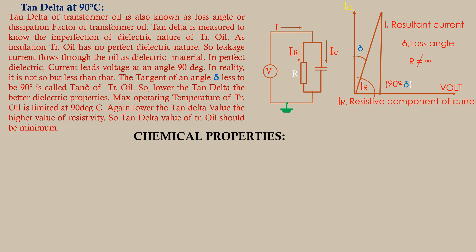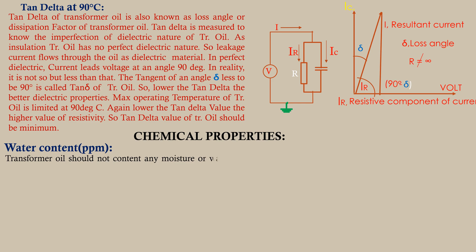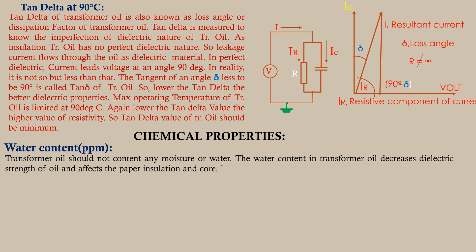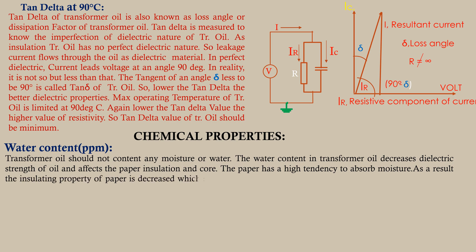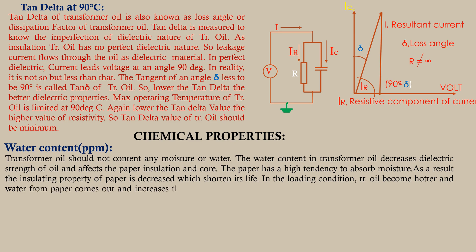Chemical properties — Water content in PPM: transformer oil should not contain any moisture or water. Water content decreases the dielectric strength and affects the paper insulation and core. Paper has a high tendency to absorb moisture, which decreases its insulating property and shortens its life. Under loading conditions, transformer oil becomes hotter and water from the paper comes out, increasing the water presence in the oil, which has a detrimental effect on the transformer oil.